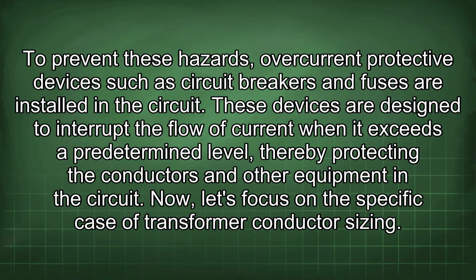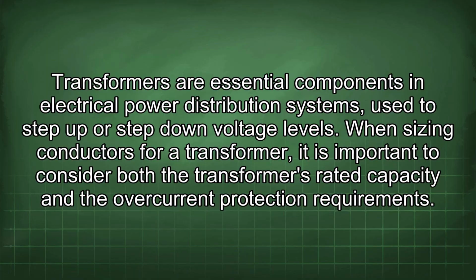To prevent these hazards, overcurrent protective devices such as circuit breakers and fuses are installed in the circuit. These devices are designed to interrupt the flow of current when it exceeds a predetermined level, thereby protecting the conductors and other equipment in the circuit. Now let's focus on the specific case of transformer conductor sizing. Transformers are essential components in electrical power distribution systems used to step up or step down voltage levels.